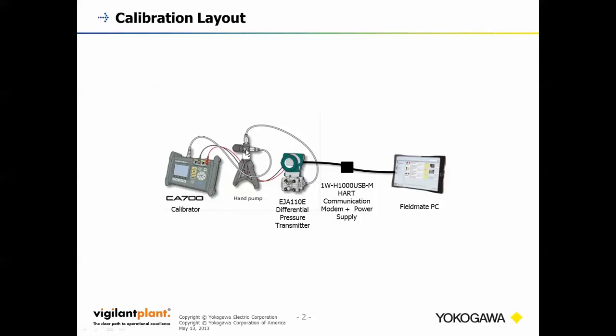We have a hand pump here that's going to be generating the pressure source that's going to be applied to both the pressure transmitter and the calibrator. So the calibrator is going to compare its pressure reading against the pressure reading of the pressure transmitter.